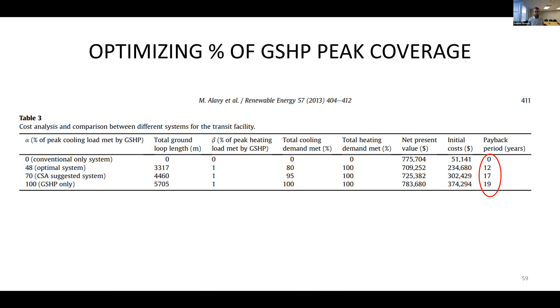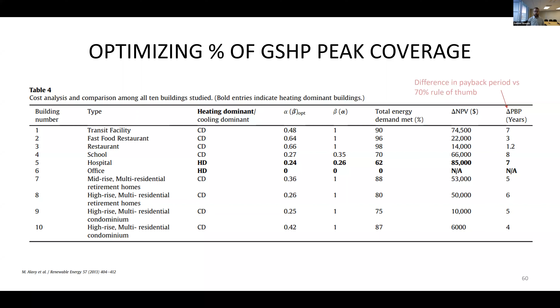Very, very significant. So the difference in payback period versus that traditional rule of thumb—they looked at a few different facilities for both heating and/or cooling dominant—and the change, this is just the difference in payback period between one hybrid ground source heat pump system and an optimized hybrid ground source heat pump system, was quite significant: 3 to 7 years. In some situations it made less of a difference, but a full year payback certainly might make the difference between a go or no-go on whether or not to install one of these systems.